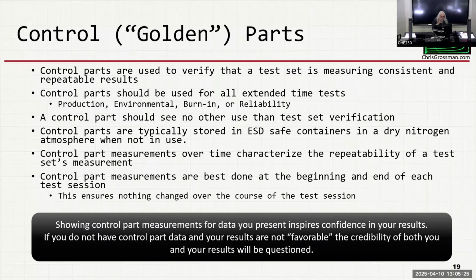If you monitor your control part measurements over time, that will characterize the repeatability of your test sets. Control part measurements are best done at the beginning and end of each test session. When you present data, you should show your control part measurements for your test set every time you present data. That gives people confidence in your results.